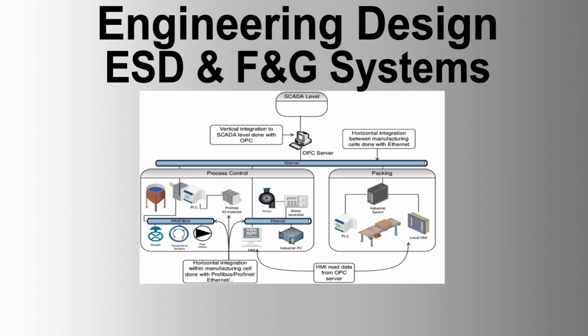System cabinet. 1. Cabinet specifications. Maximum cabinet size, 800 mm W by 800 mm D by 2100 mm H. Standalone cubicles housing a fully integrated emergency shutdown and fire and gas detection system. Dual redundant TUV certified programmable logic controller (PLC) system suitable for SIL3 applications. Separate hardware for ESD and F&G, including dual serial data communications equipment and dual power supplies. Front-only access with swing frame arrangements and bottom cable entry. Cabinets shall be tagged as per project tagging philosophy.